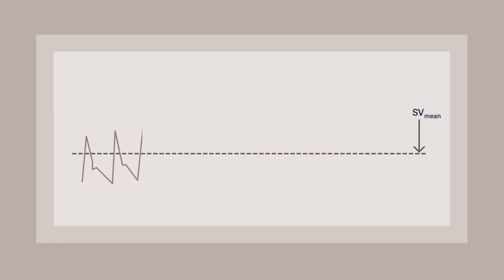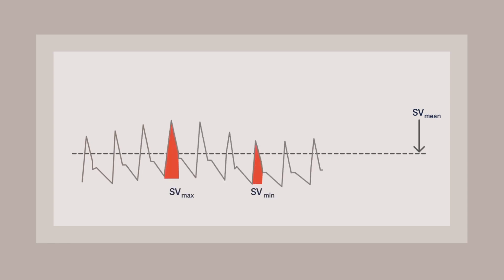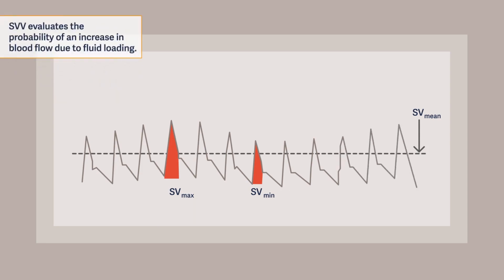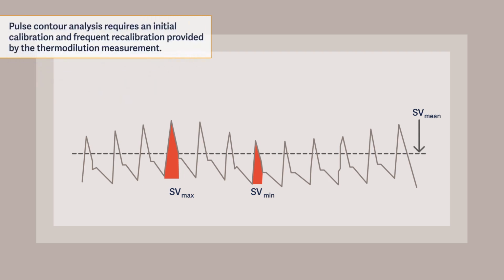Additionally, the stroke volume variation, or SVV, is also derived by the pulse contour analysis. It is a parameter on volume responsiveness that evaluates the probability of an increase in blood flow due to fluid loading. Pulse contour analysis requires an initial calibration and frequent recalibration that is provided by the thermodilution measurement.